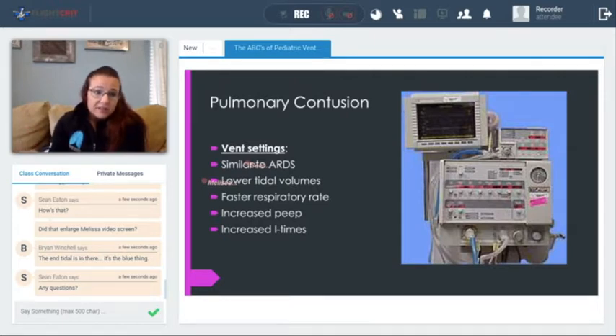So all I have to do is hit my I time button, my I to E ratio will come up, and then I can use my toggle switch and turn up that inspiratory time. So if you were on a kid, you were probably somewhere around 0.5 or 0.6. You can start dialing up that I time, and you are starting to move toward a 1-to-1 I:E ratio.